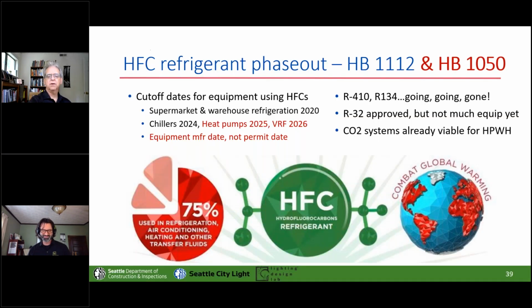Okay, a note about refrigerants. Just this year, the legislature said, okay, starting with heat pumps made in 2025 or for VRF systems in 2026, you're going to have to come up with refrigerants that have a global warming potential below 750, which counts out the ones we typically use today. So word to the wise, start planning now and get in touch with all your product reps and start finding out who's got R32 or other advanced refrigerants on the market, and go for those when you've got them.